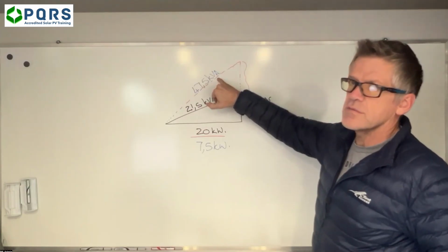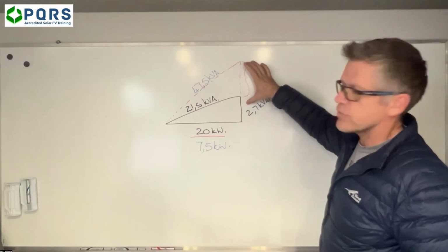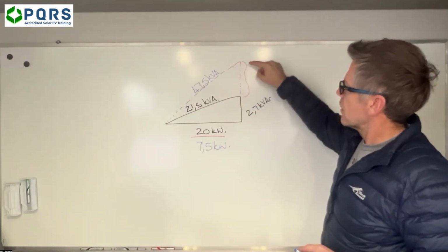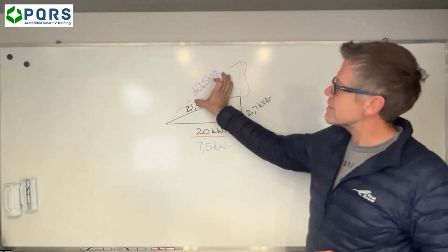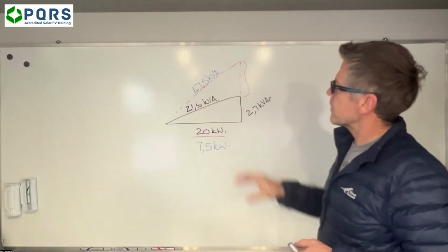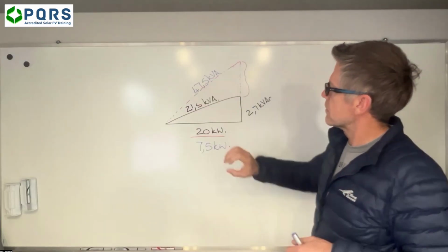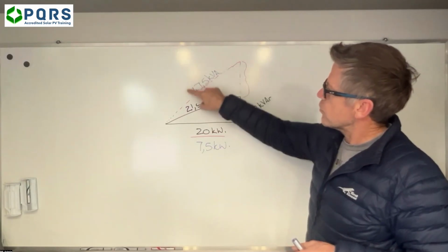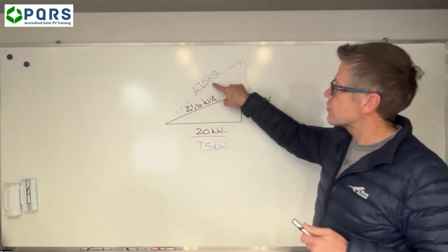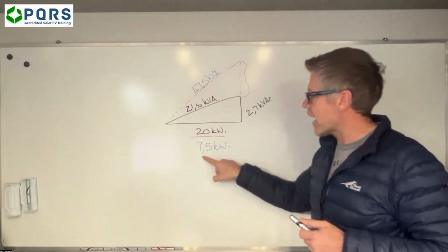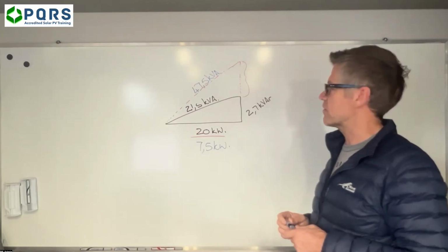You guys see, with the low load that we have and the massive kVA value we have over there, the only reason for this could be that we must have a very big reactive power component. This power component over here is responsible for the extremely high apparent power that we are busy drawing on the site. So we've got a 47.5 kVA load on the transformer, even though the actual load of what we are using on site is only 7.5 kilowatts.